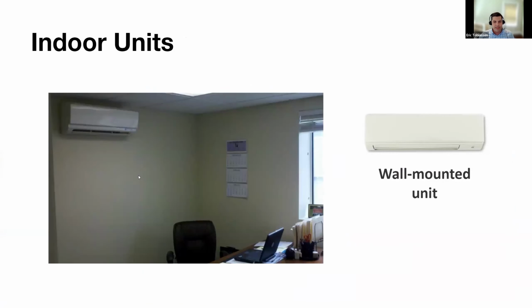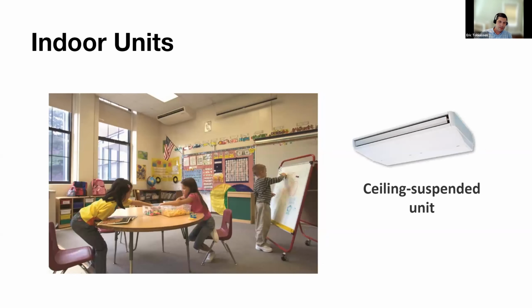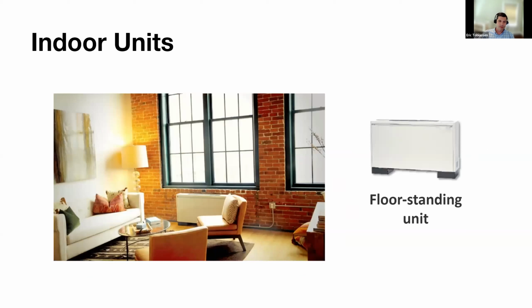And now we're just going to look at some of the different styles of indoor units. These are pretty much the same amongst all heat pump manufacturers. So you have your wall mounted unit. This is really good if you're doing a retrofit application or you just don't have enough ceiling height to put in a cassette. Ceiling suspended unit. We typically see these in retrofits as well, where you don't have access to the ceiling. And these are just butted up right below the ceiling there. Floor standing units. Again, you don't want anything on the wall or you have lower ceiling heights, this is a good option. So these just sit right on the floor.